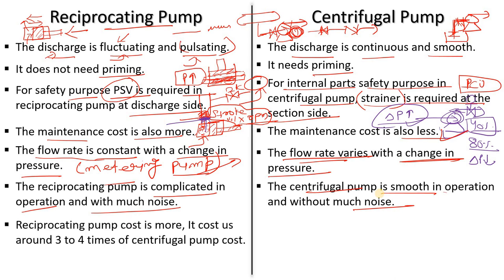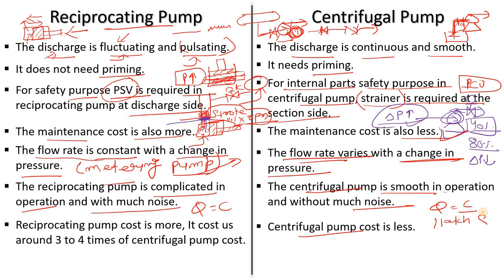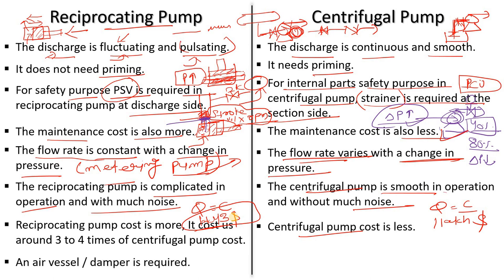From a cost point of view, for the same flow rate, if a centrifugal pump costs one lakh dollars, a reciprocating pump would cost around three lakh dollars. This is because the centrifugal pump is simple in construction, while the reciprocating pump has more complexity.